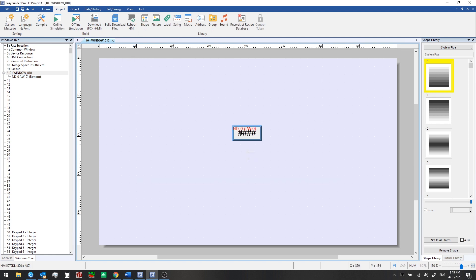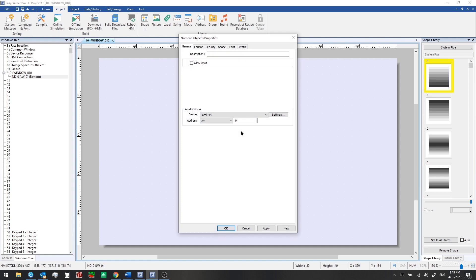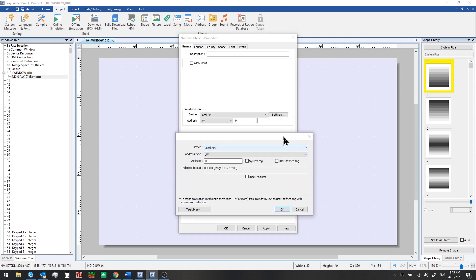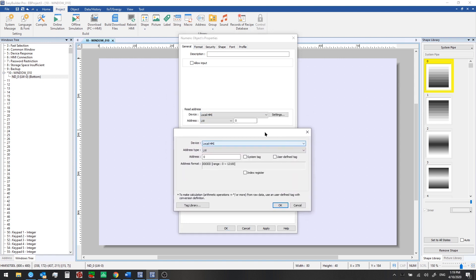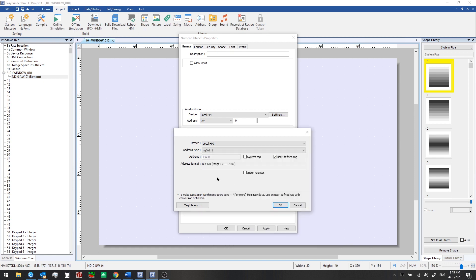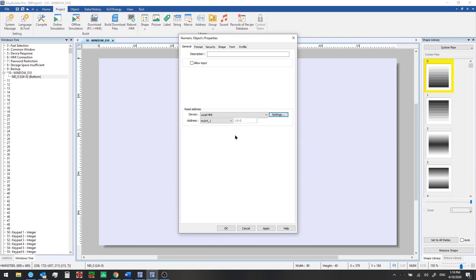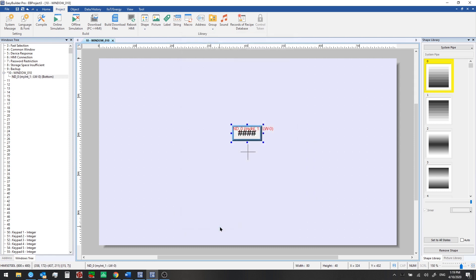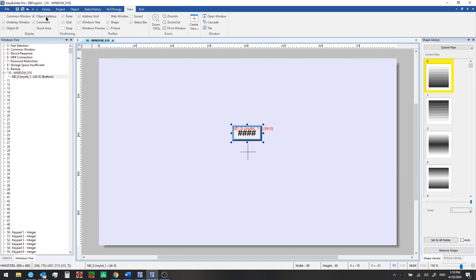And let's go ahead and double click on this numeric object one more time. We can get back to the properties window and change the settings. Now for the read address, we'd selected local word zero. But if we click on this settings button to the right, we have more advanced settings for the read address that we can pick from. So let's check user defined tag here. And now if we click on address type, we can scroll down and we can find our user defined tag that we just created. So let's click OK there. Now we've selected that my int one and click OK. And then we'll click OK one more time. And now we see that and that shows up both over the object itself in the object address. And over here in the window sidebar, it shows up too. It has the name of the tag and it has the associated register that we're using.